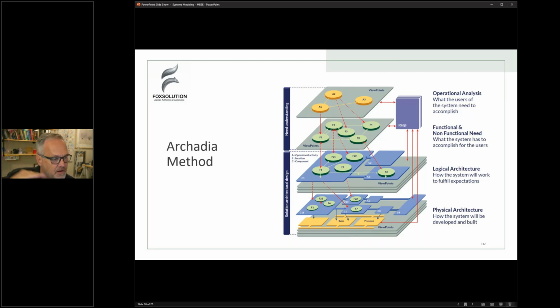So logically, we're trying to say how the device works together, but we haven't physically understood what the embodiment is going to look like. And then finally, we get down to this physical architecture level where we're identifying printed circuit boards, sensors, interfaces that are not abstract. We have a USB interface here, we have a cloud interface here. So once we get down to that physical architecture, we can actually do risk on it because we understand what the discipline is and what parts are associated with any of the analysis. So I'm going to walk you through these levels in the systems modeling tool so you have a better sense of what it looks like in the application. But just know that we're going to go down 4 levels to get to that physical architecture. And this is a method.